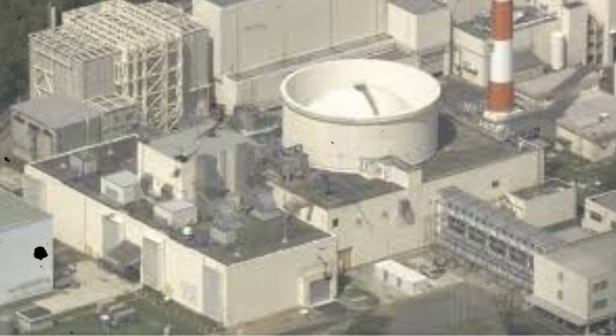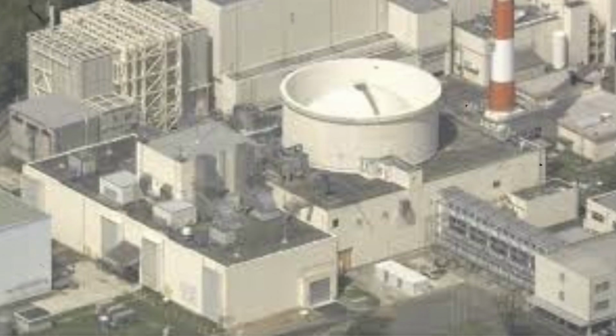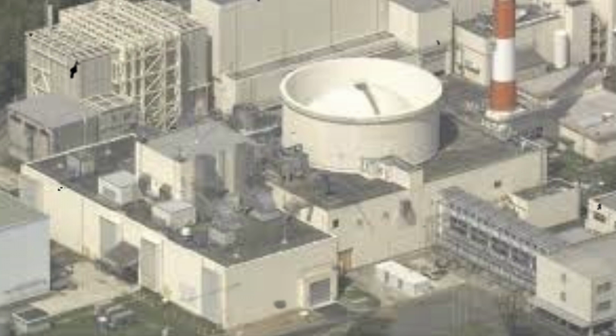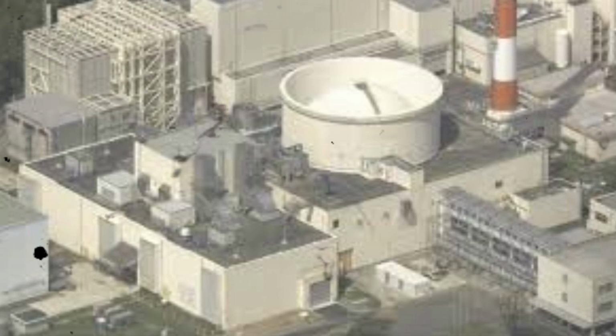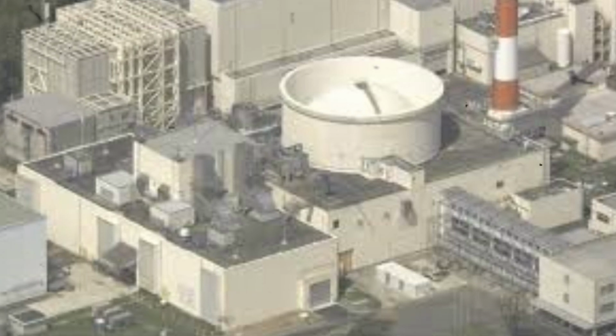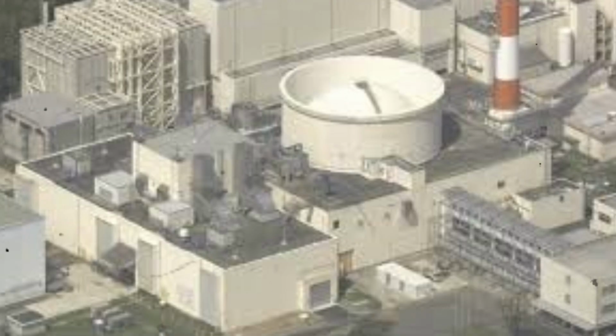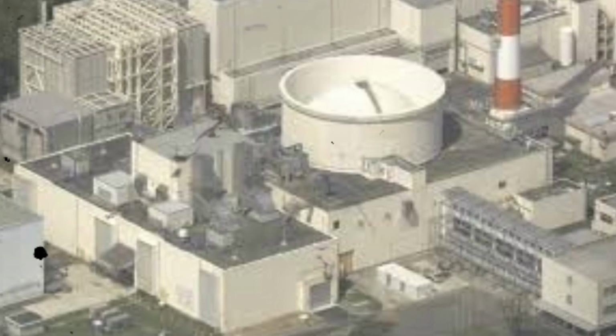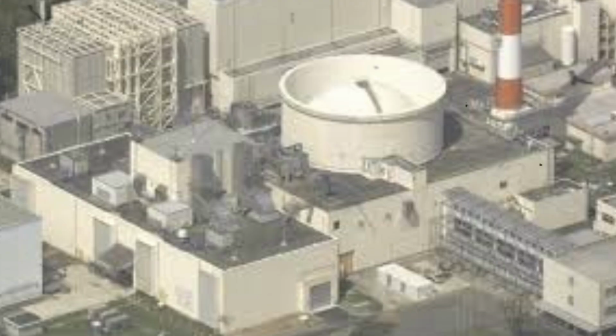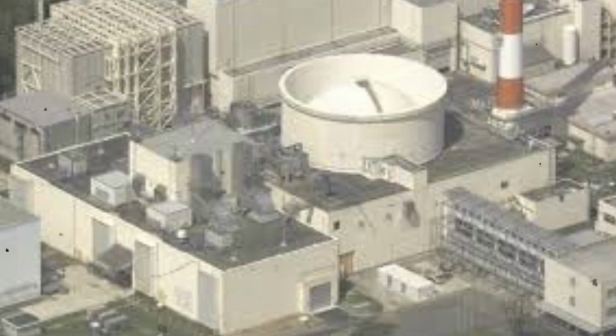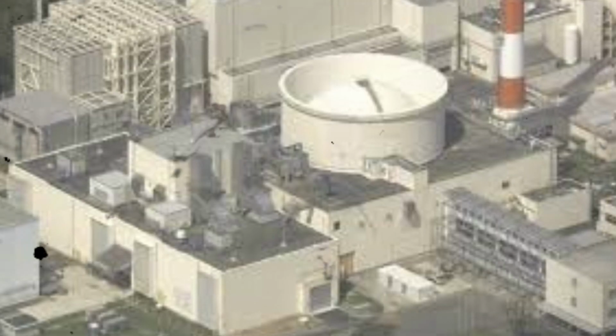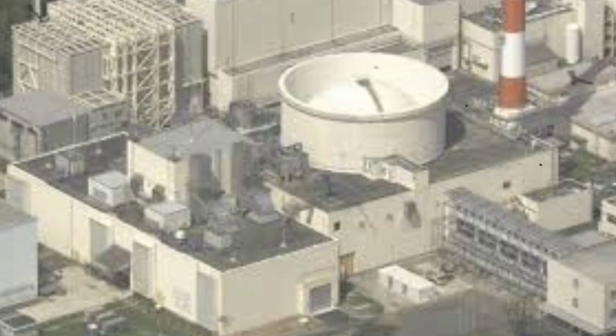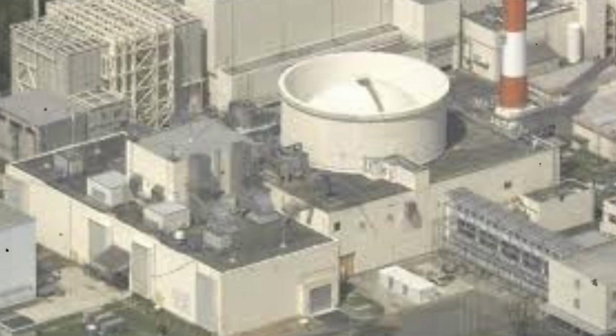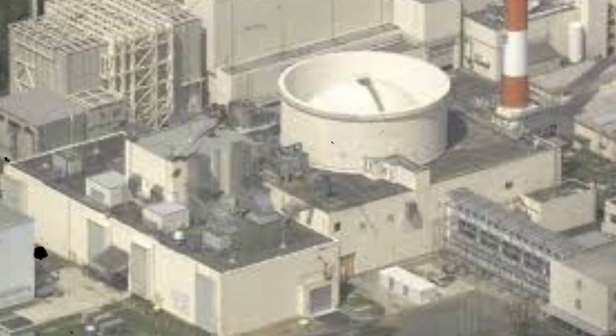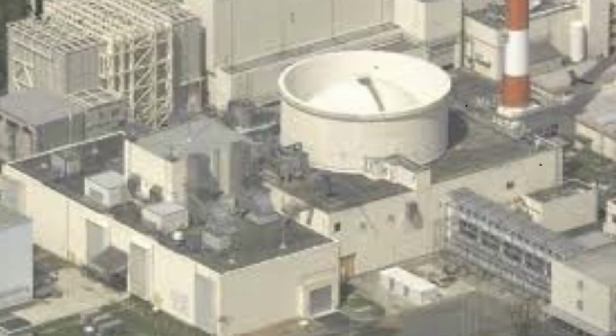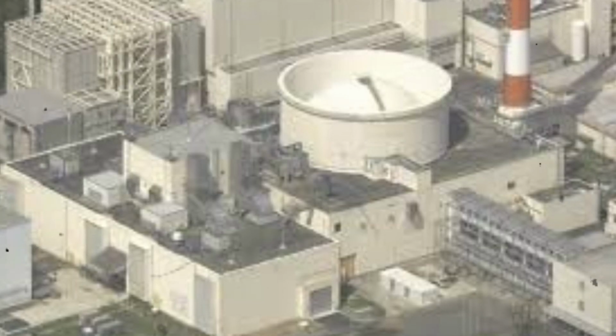The temperature increase resulted from sodium escaping through a failed thermocouple well, but no instrument could directly identify this specific failure mechanism. The fire detection responded to sodium combustion, but could not quantify the leak rate or predict leak progression. The leak detection confirmed sodium presence, but provided no information about the failure location or structural condition of the affected component. Microscopic examination would later reveal that the thermocouple well failure had been months in development.